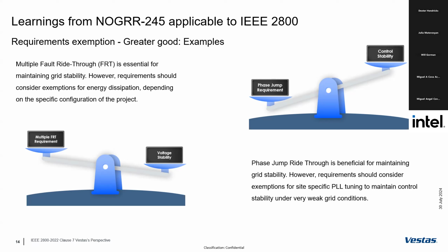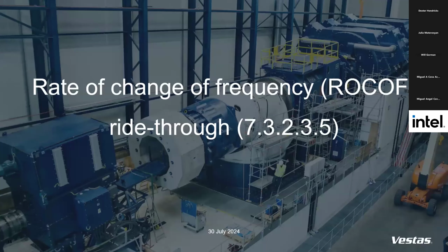Same happens with the voltage phase jump and the control stability. We might have to tune a PLL in a very specific way when there is a very weak grid to reduce the constants of that PI controller and maintain the voltage stability, but we might not ride through the 25 degrees. So it's a trade-off that is very important to keep in mind between the project specifics and the actual product capability.